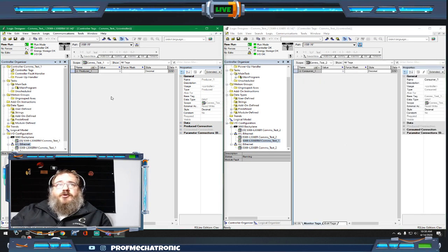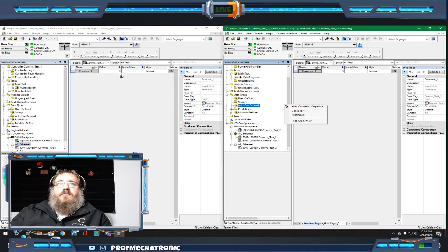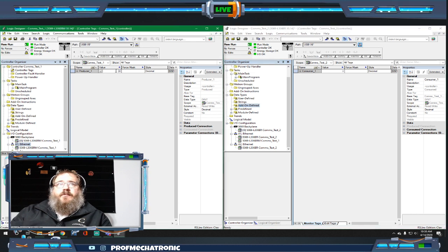All right, so now we have our producer and our consumer. Well, obviously our producer is going to be what changes the tag value, and we should see the consumer update with the numbers that we put. So here we're going to put any number in, so I'm going to put a 5 in. Now when I hit enter, we should see that update on the consumer side.